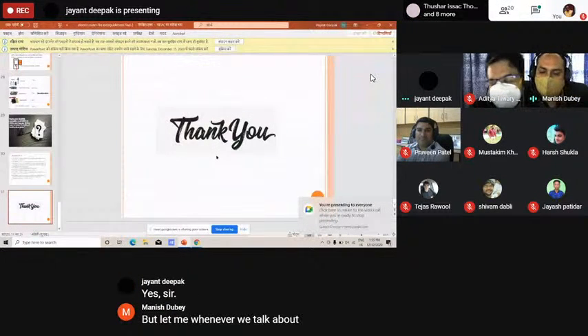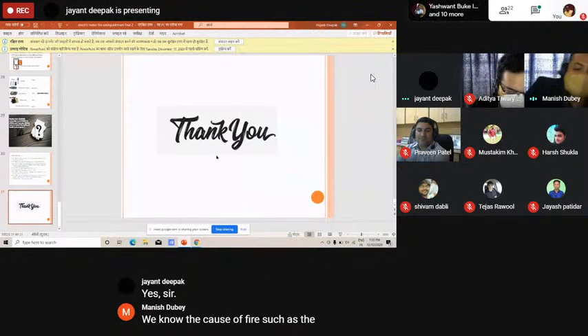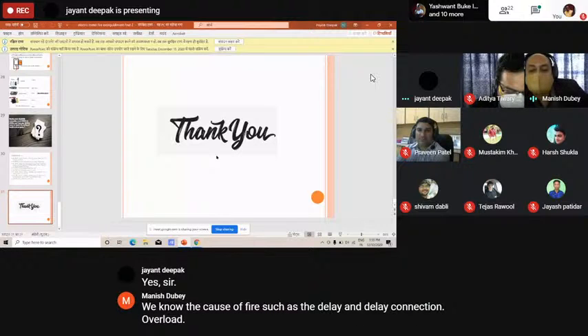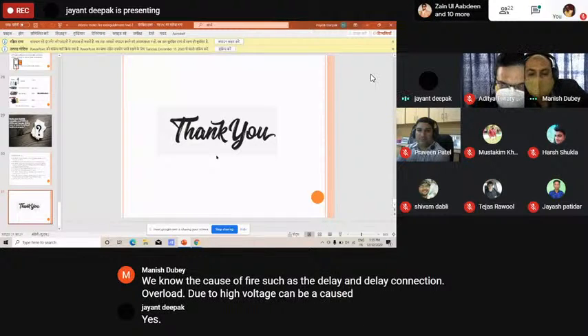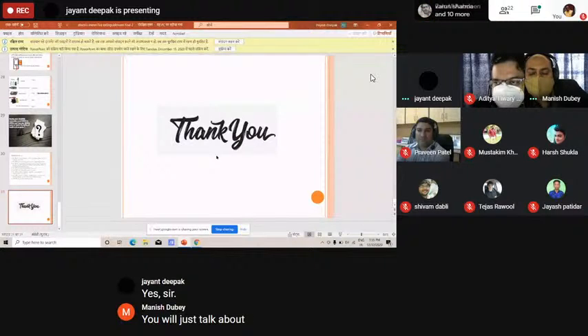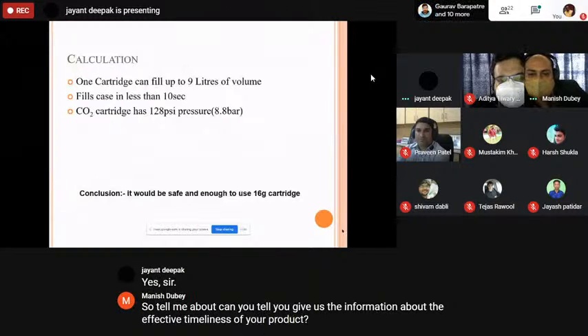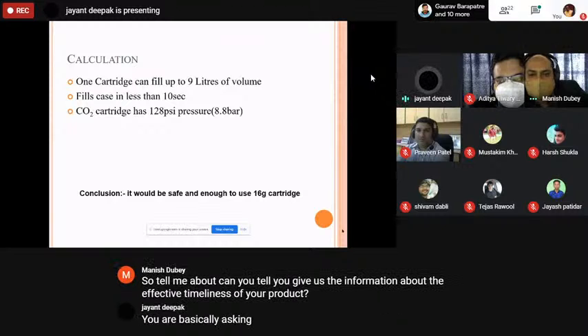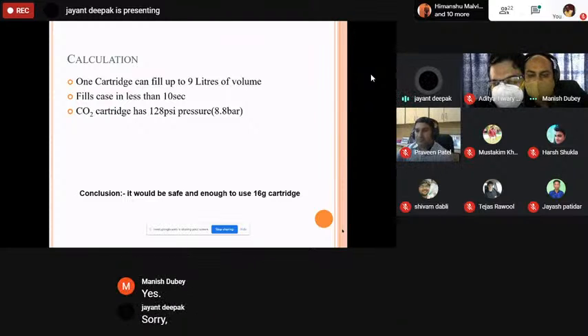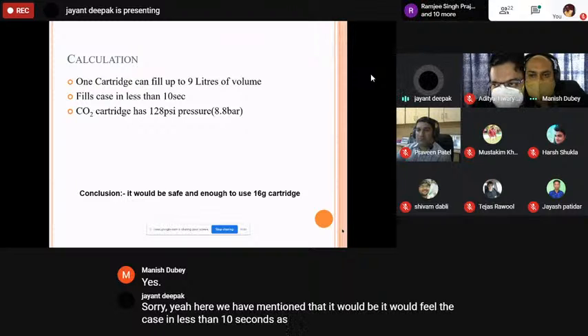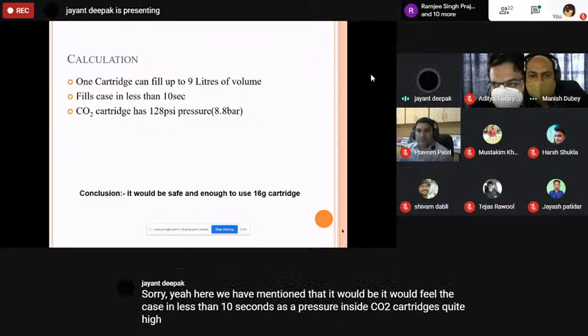Whenever we talk about electrical fire, we know the causes of fire, such as loose connection, overload, and high voltage can also be a cause. Give us the information about the effective timeliness of your product. So you are basically asking what will be the time required to extinguish the fire. Yes, sir. Here we have mentioned that it would fill the case in less than 10 seconds, as the pressure inside the CO2 cartridge is quite high, 8.8 bar.